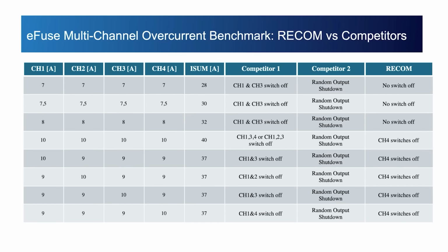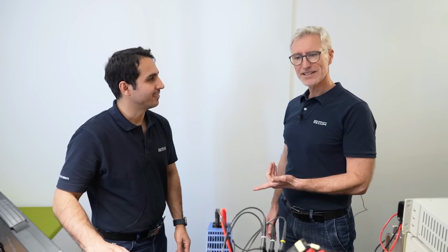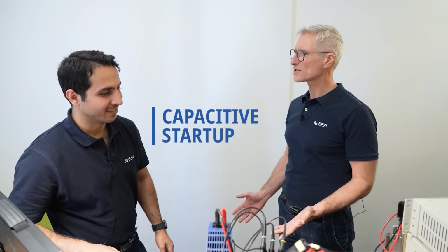So can you show us how the competitors perform when the power supply is in overload? So if the loads together draw too much current? Now you see here, completely the function, there is no sequential shutting down of the outputs. There's no priority, no intelligent power shutdown for outputs. Okay. So it's completely random. This is completely random.